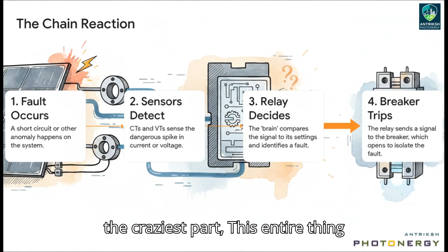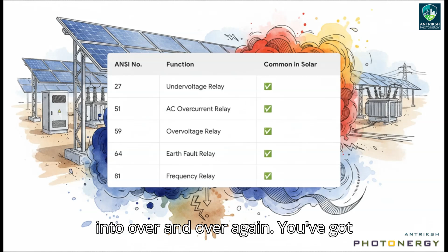It's time to go inside the brain of the whole operation, the protective relay, and decode what it's doing. This table is your pocket cheat sheet for the field. You're going to see these ANSI numbers everywhere, on drawings, on relay faceplates, and in solar these five are the ones you'll run into over and over again: undervoltage, overcurrent, overvoltage, earth fault, and frequency. There's a good reason these are so common.